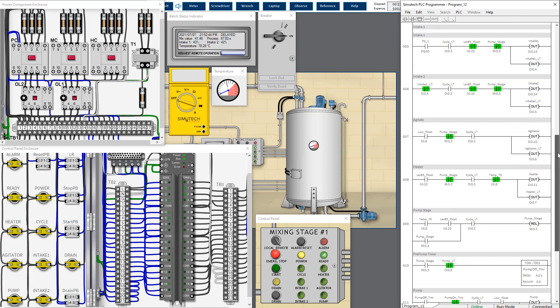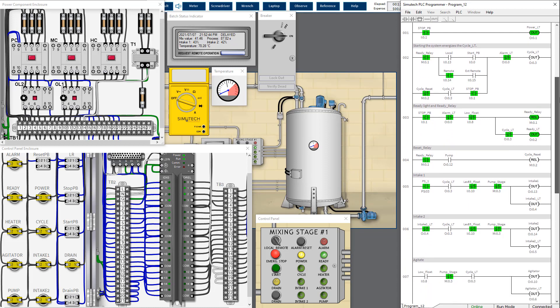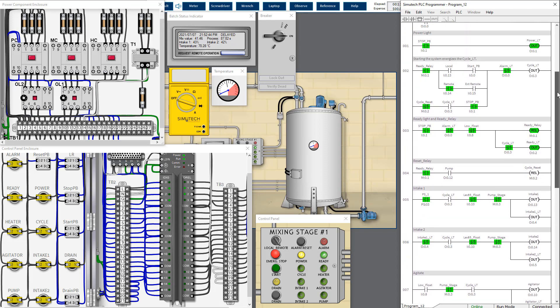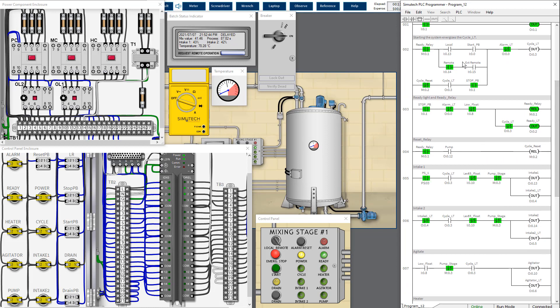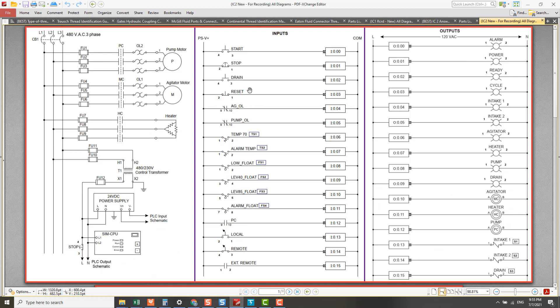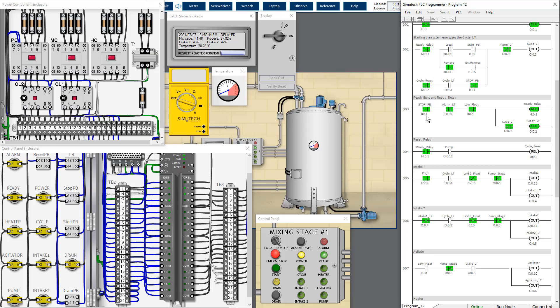In order to do that we have to understand the program. The stop push button is always energized — the stop push button here is the emergency stop. The external input device stop button or EMO is always connected as normally closed, so current always energizes the PLC input channel at channel one. Because it is always energized, the virtual relay switch is triggered to close.